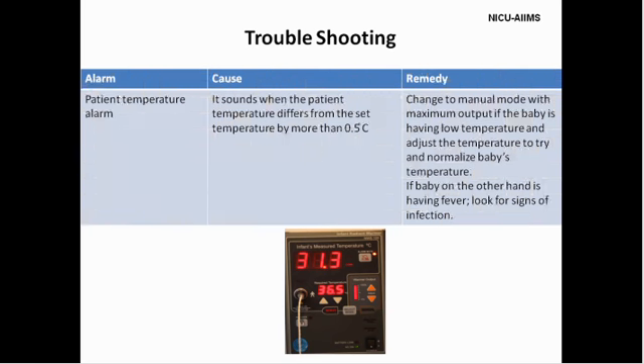The patient alarm may be activated when the difference between the baby's temperature and the set temperature is greater than 0.5 degrees Celsius. This happens when the skin probe is dislodged from the baby or is loosely attached. Rectify the underlying cause. Press the alarm silence button. At times, we may have to change to the manual mode with maximum temperature output if the baby is having low temperature, and adjust and normalize the baby's temperature. If, on the other hand, the neonate is having fever, we have to actively look for other signs of infection.